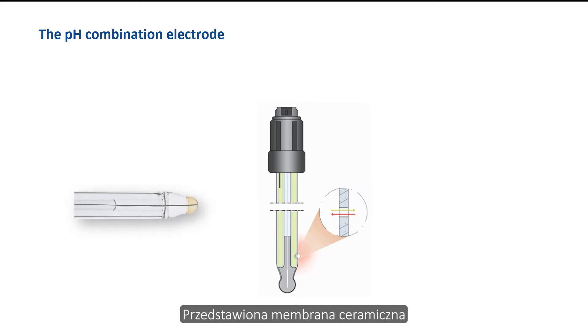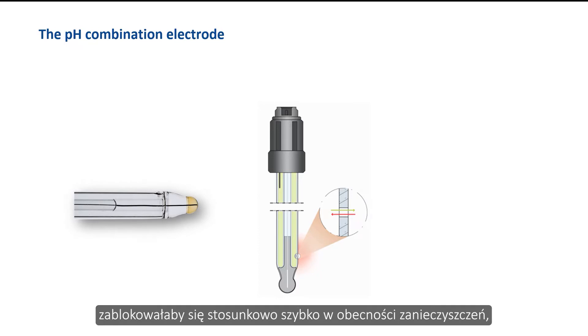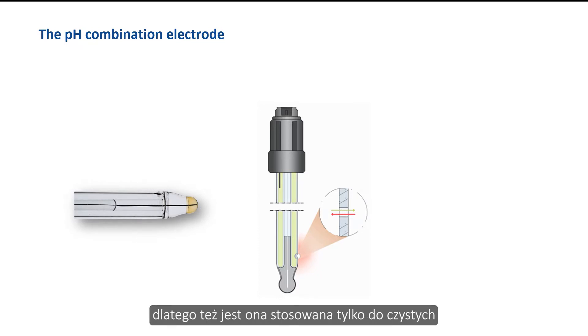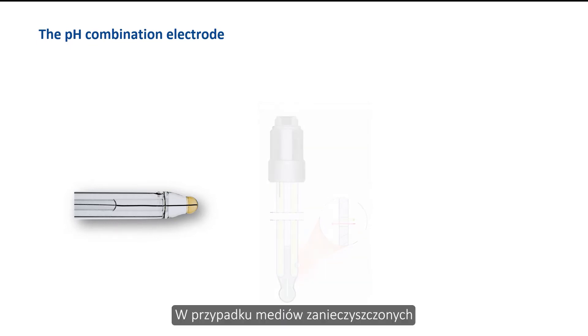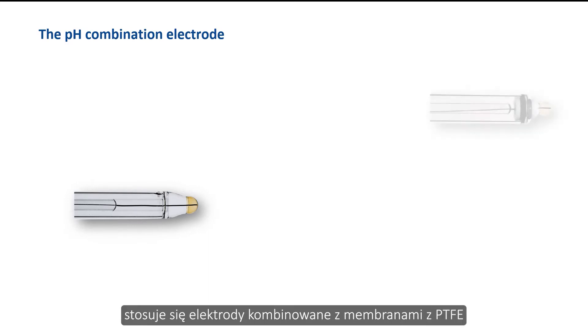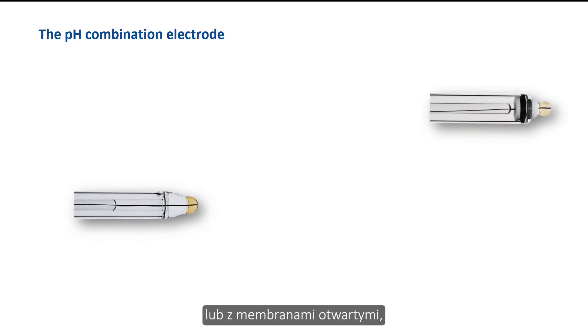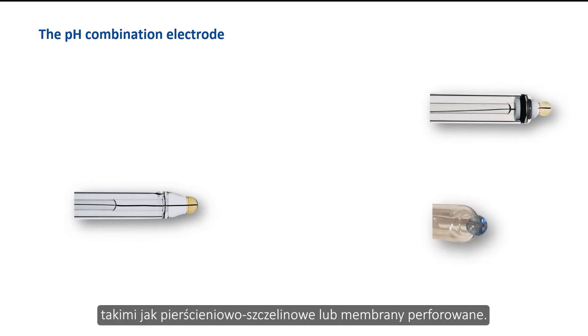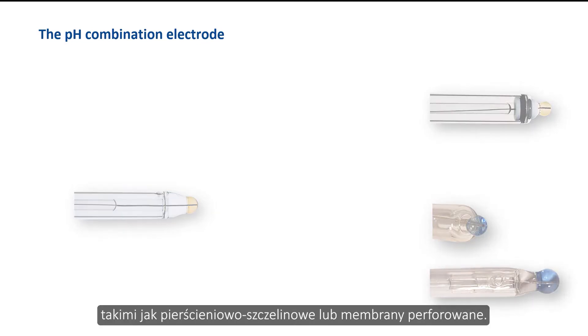The ceramic diaphragm would block relatively quickly in the presence of contamination, which is why it is only used for clean or slightly contaminated media. For contaminated media, combination electrodes with PTFE diaphragms or those with open diaphragms such as annular gaps or perforated diaphragms are used.